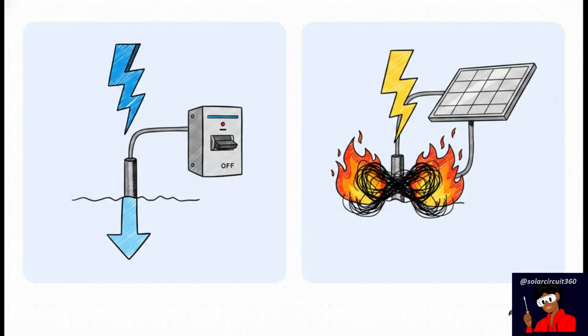A lot of folks look at a thick copper wire running down to a metal rod in the dirt and think, awesome, the system is grounded, we're completely safe. But a ground isn't just some static piece of metal. It's an active, dynamic safety highway. When something goes wrong, that highway is the exact path dangerous fault currents have to take.